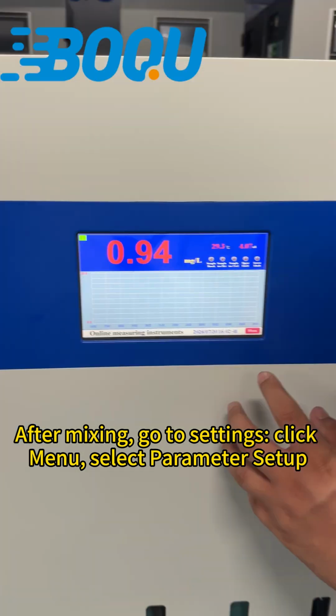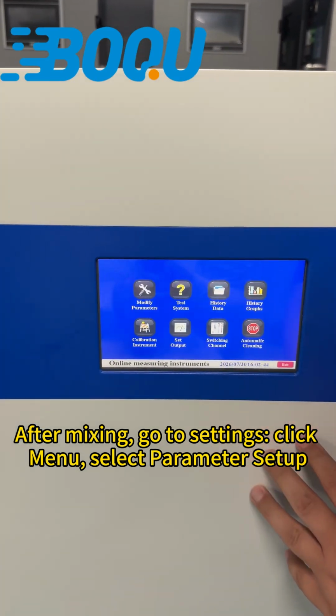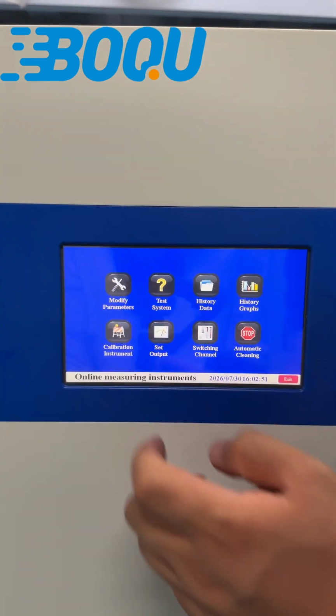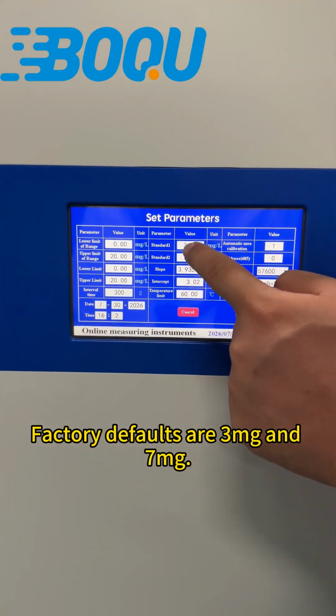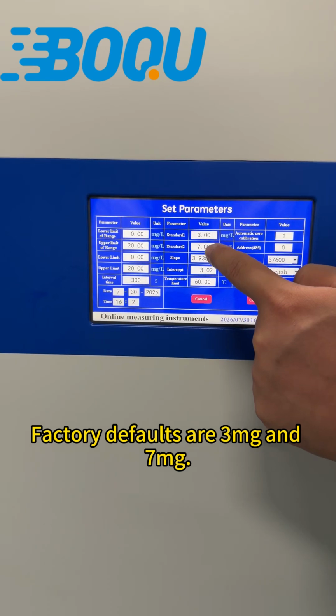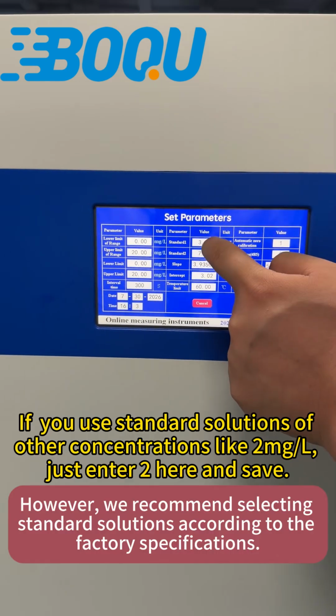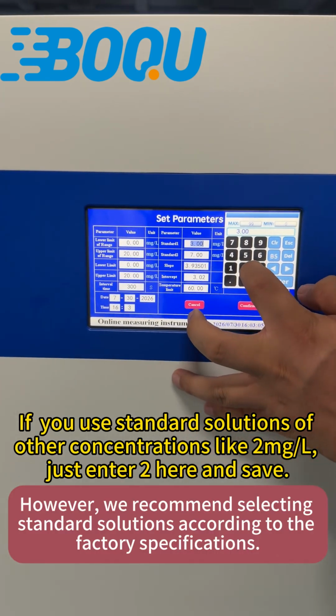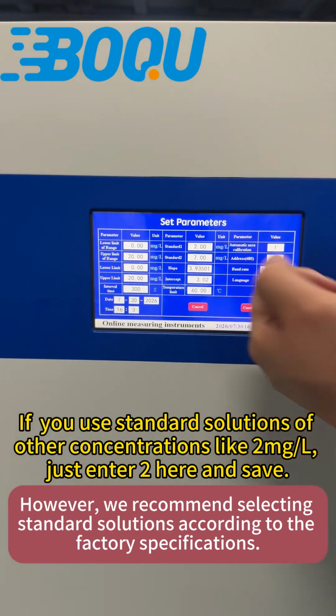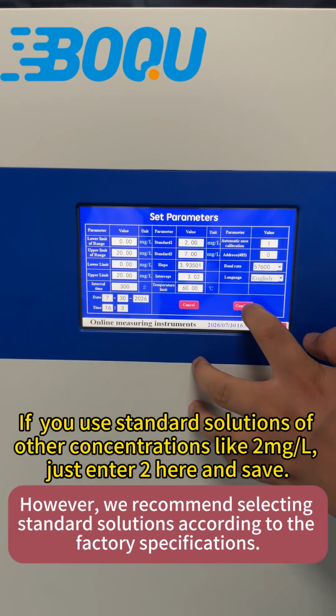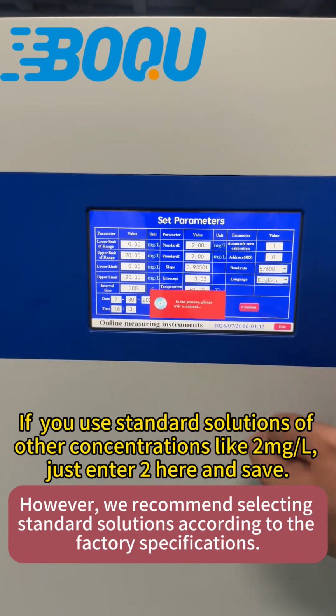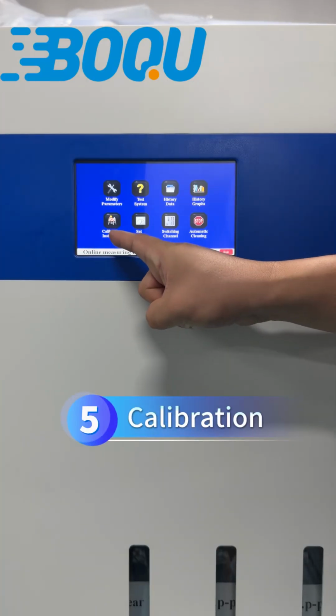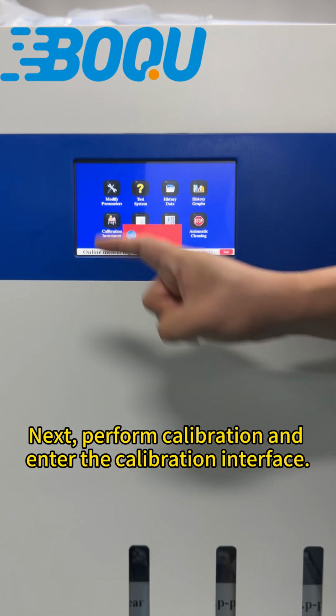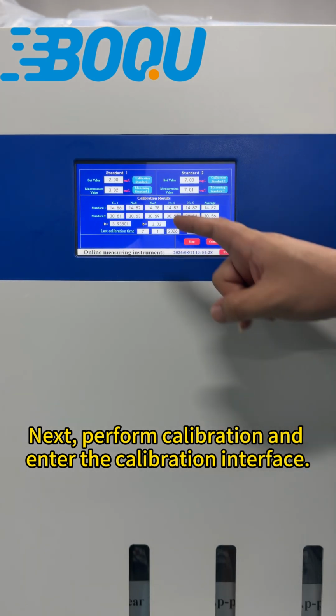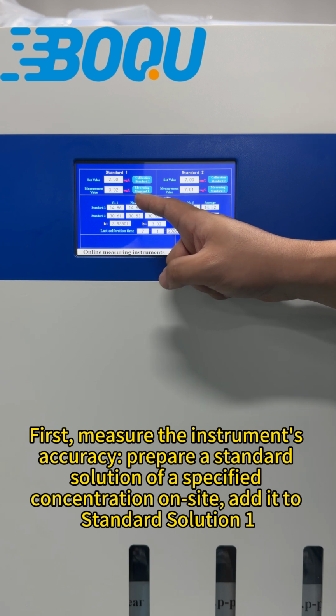After mixing, go to Settings, click Menu, select Parameter Setup. Factory defaults are 3 mg and 7 mg. If you use standard solutions of other concentrations like 2 mg per liter, just enter 2 here and save. Calibration. Next, perform calibration and enter the calibration interface. First, measure the instrument's accuracy.